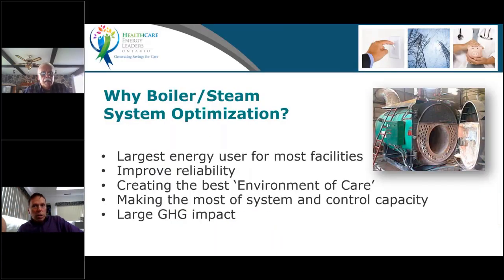So first thing first, let's put things in perspective here. Boilers and steam systems in healthcare, especially in hospitals, when we talk about steam, are very large users. If you look at the boiler plant, it's usually the largest energy user in a healthcare facility. Long-term care, for example, would probably have more hot water than steam, based on my experience. Some of them will have steam, but the heating and the boiler, which would be a hot water boiler, do remain, even in long-term care, the largest end use, making up 50%, sometimes more, of the total energy usage.